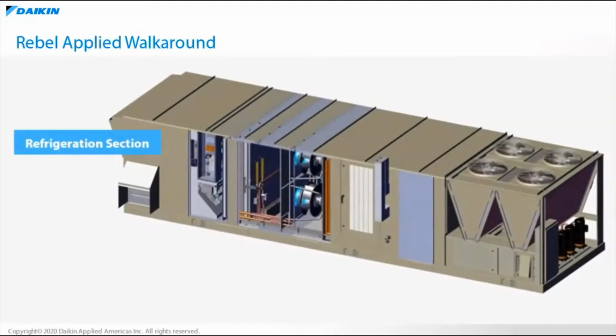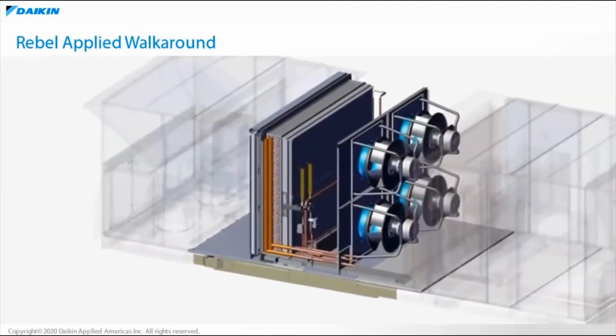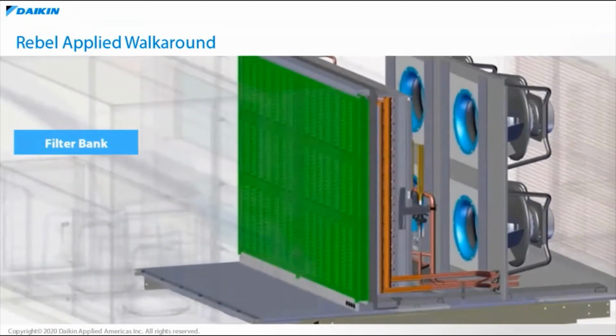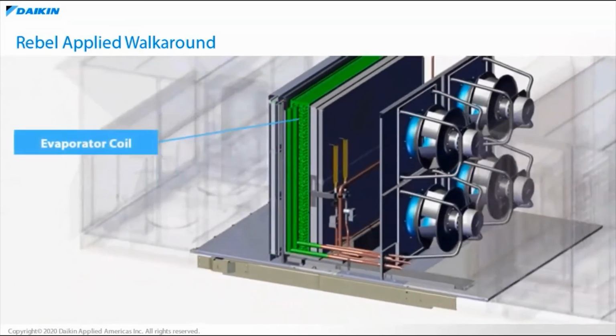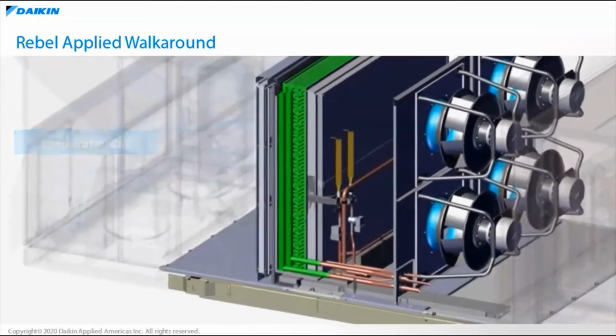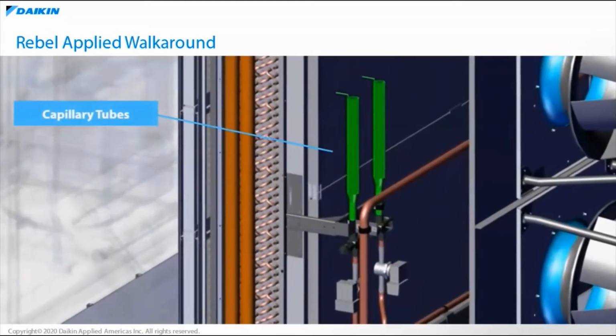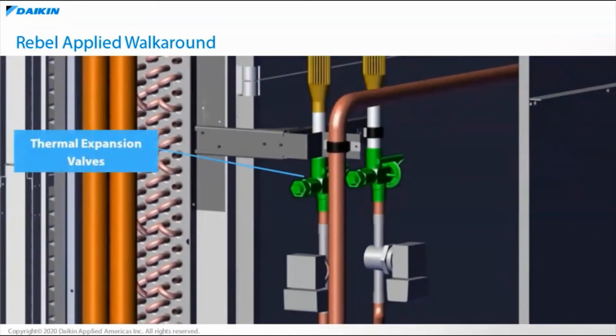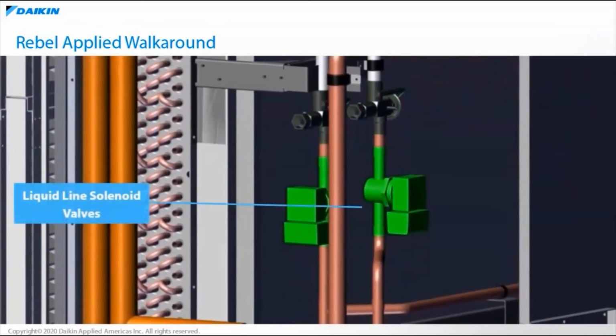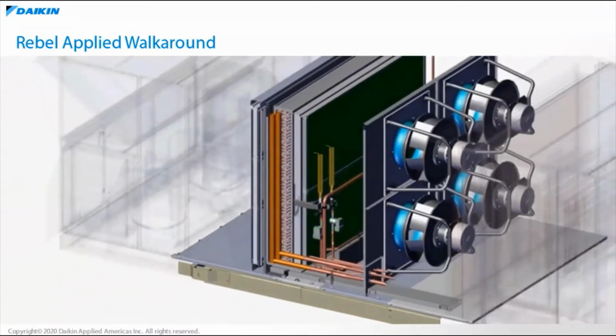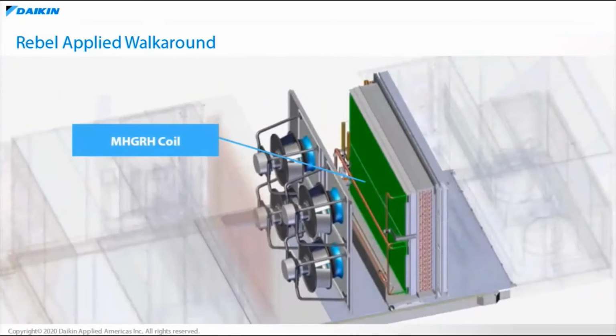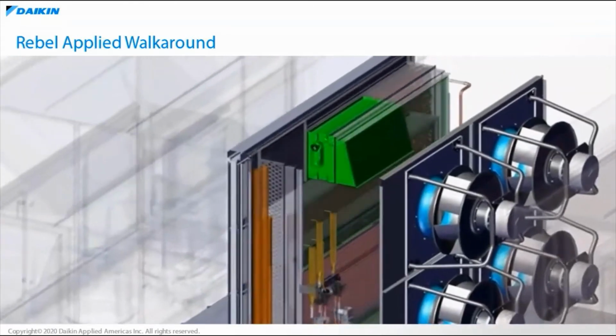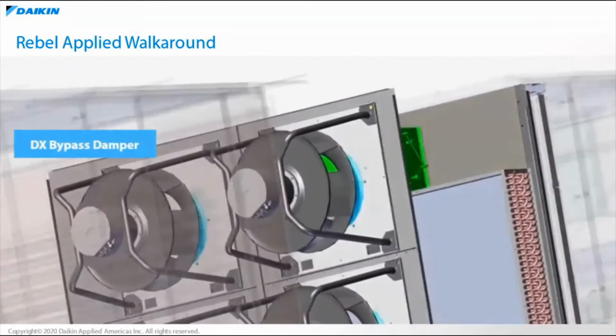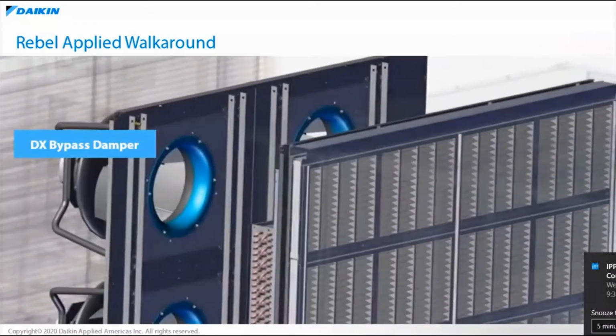Next, we will review the refrigeration section. A filter bank supports the use of multiple filter sizes. After the filters is the direct expansion DX evaporator coil. Adjacent to the evaporator coil are refrigerant capillary tubes, expansion valves, and liquid line solenoid valves. An optional subcooled liquid reheat coil and/or modulating hot gas reheat coil is next. Also optional for specific size evaporator coils is a DX bypass damper, which provides optional reheat during certain periods of dehumidification.